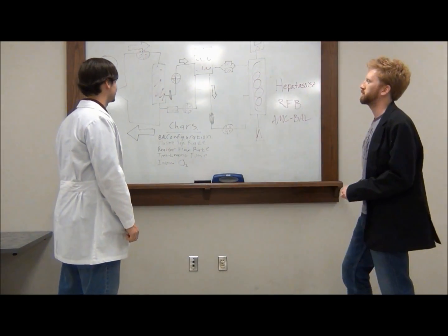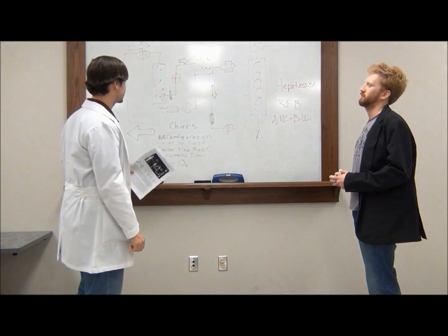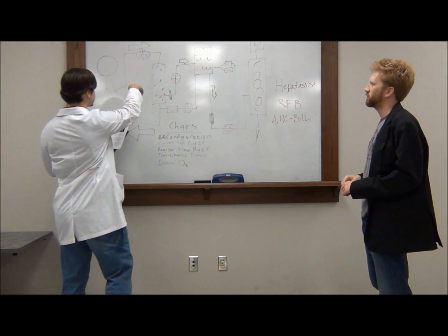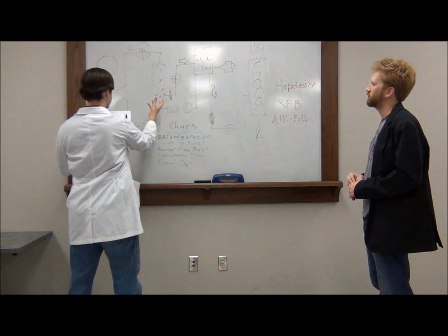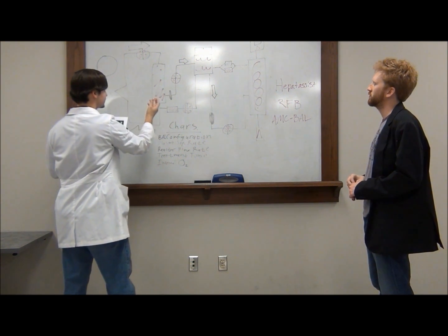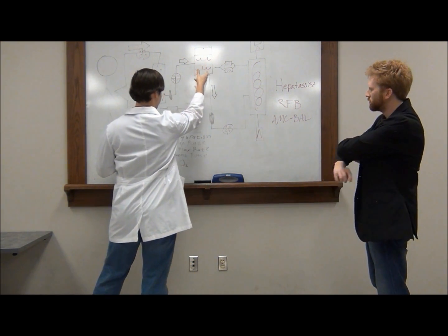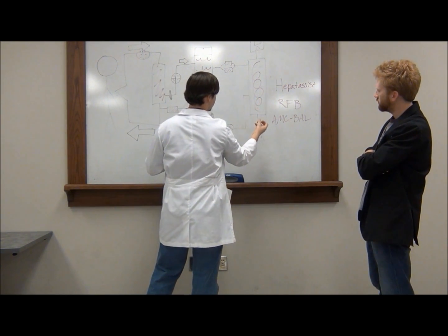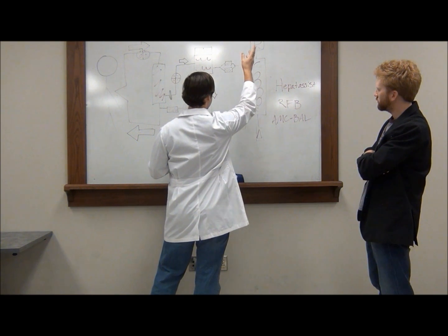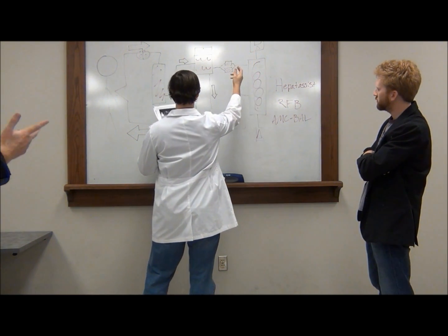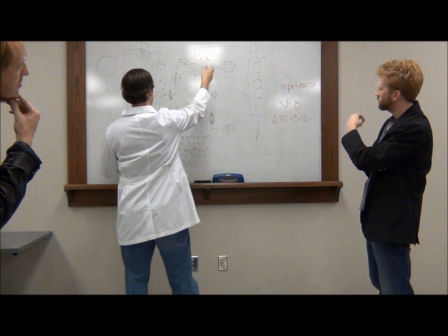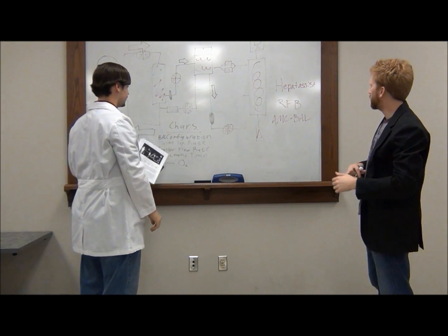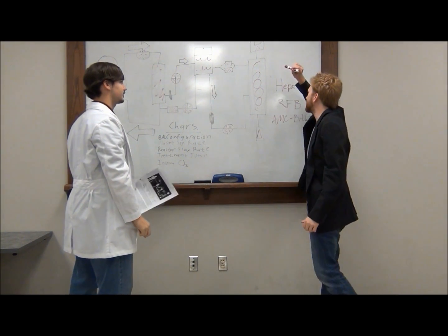What do we have here? Well, this is a basic configuration for a bioartificial liver. First, the blood comes out of the body and it's pumped into the plasmapheresis chamber where it separates the blood from the plasma. The plasma then runs into the plasma holding chamber. It is then heated and sent into the bioartificial liver where oxygen is added and CO2 is taken away from it. And then the plasma passes through some filters, back into the plasma reservoir, and then back into the body.